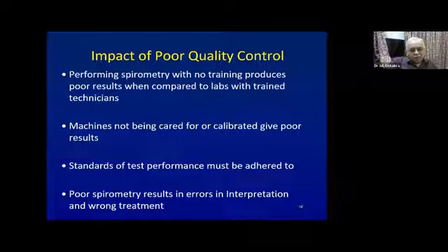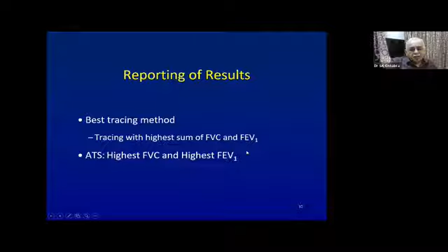So quality control is very important, and if it is not done properly, either the maintenance of the equipment or the performance of the test, then we get poor results. Then how do we report the results? We take the curve where the sum of the FVC and FEV1 is the highest. Among all the acceptable tracings which have passed the repeatability criteria, we add up FVC and FEV1. The loop which gives the highest sum is taken as the patient's best result, and that is printed for interpretation.